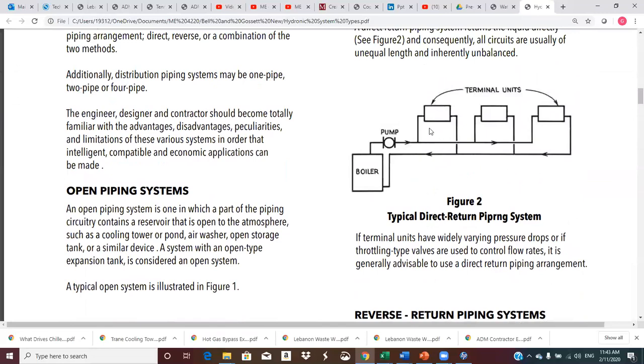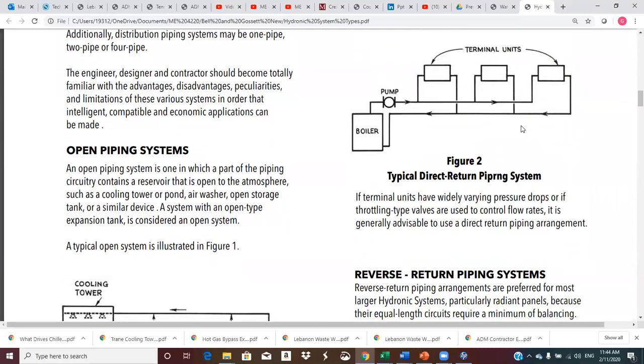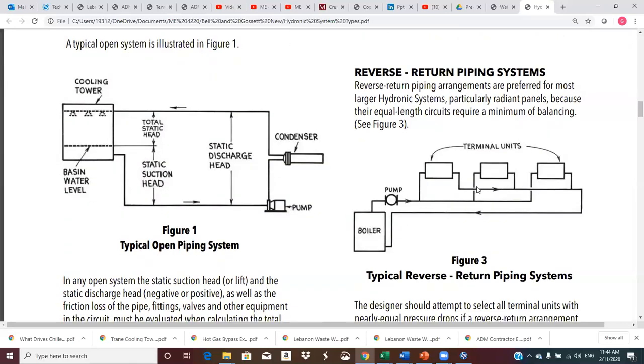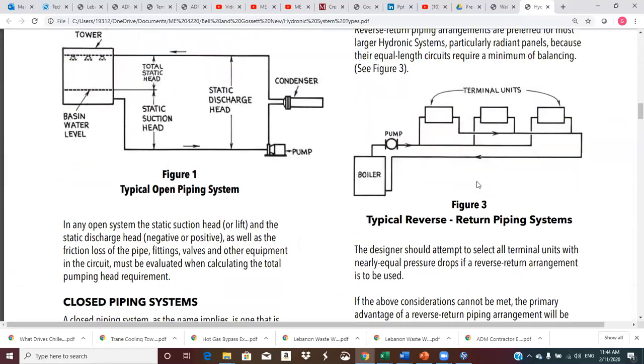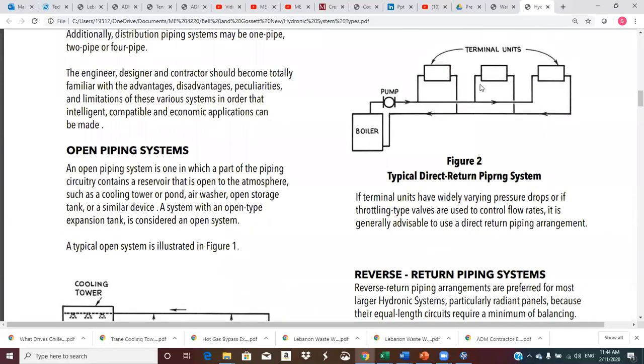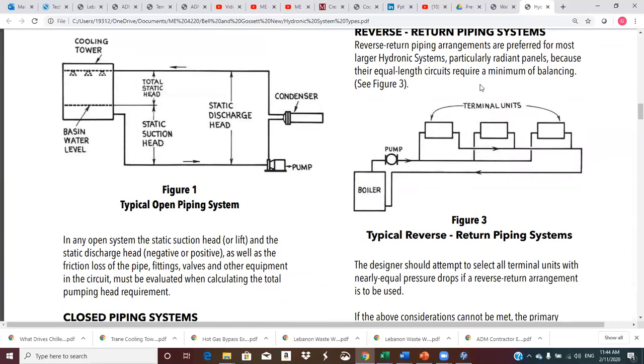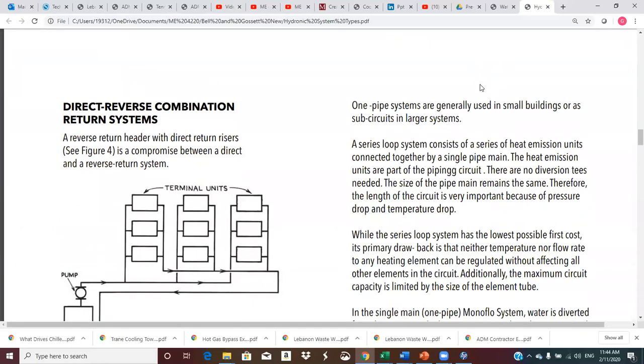Up here, if these coils all have the same pressure drop, you're going to have to use a balancing valve to put extra resistance in this short path, or it will get most of the flow, and this poor guy out here on the end won't get anything. And so that's really the benefit. It makes it easier to balance this, but you have to buy more pipe. On this one, it's harder to balance at times, but you buy less pipe. So that's kind of the way that goes.